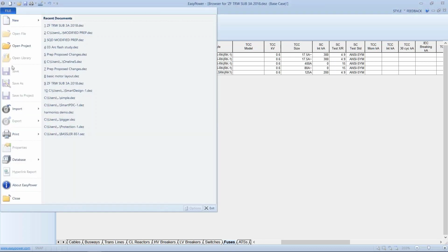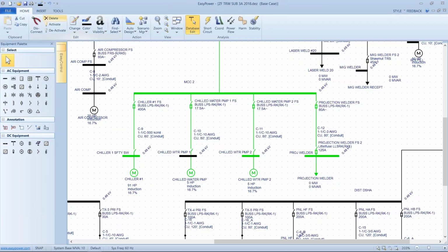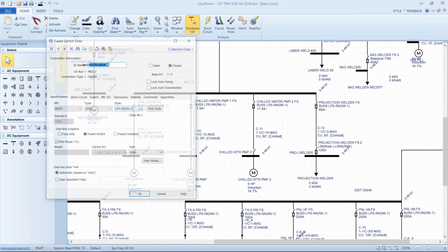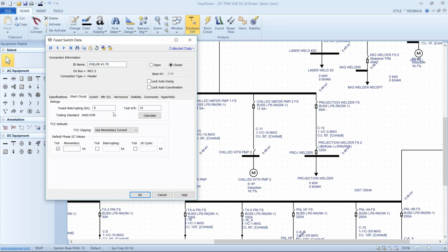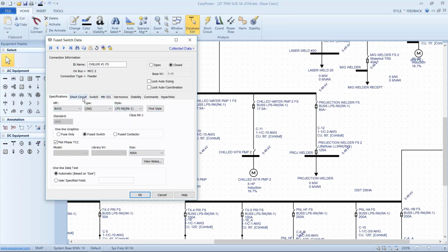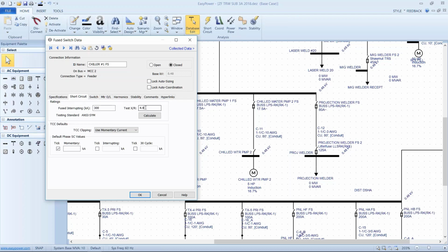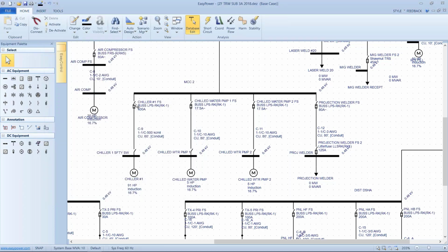So again, let's go back. I'm going to close this report and look at one of these fuses. And what I see is I've set up the fuse with the manufacturer and the size, but when I went to short circuit, the person that did the modeling didn't click calculate. And if you've seen any of my presentations, when I'm at this point, I want to click calculate and see these numbers change. That tells me, okay, Jim, I found the part number that you gave me. There's a manufacturer's data sheet in the library, and the manufacturer tested this component with an X over R value of 4.9. The tool will then use that value and compare it against the current and the X over R value that it encounters when it runs equipment duty in this system.